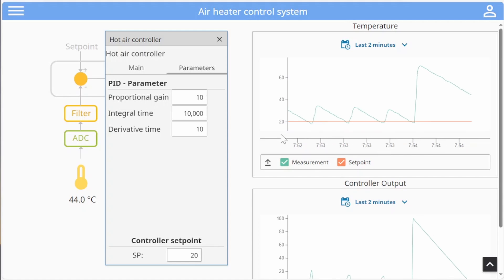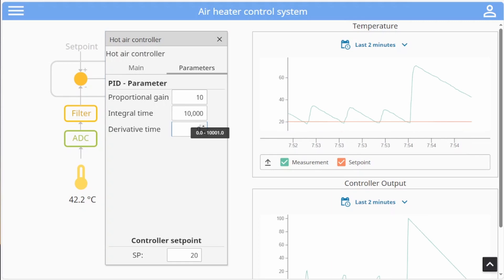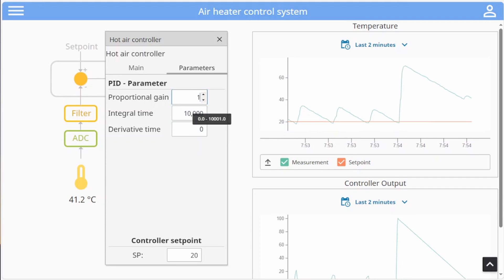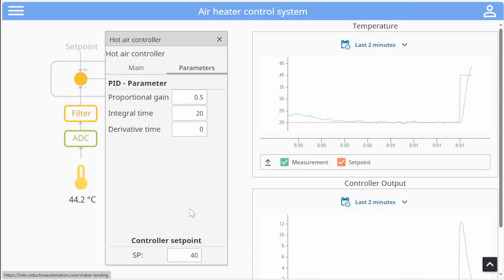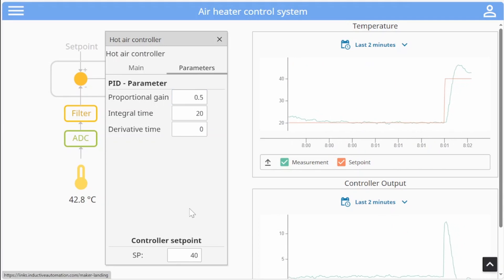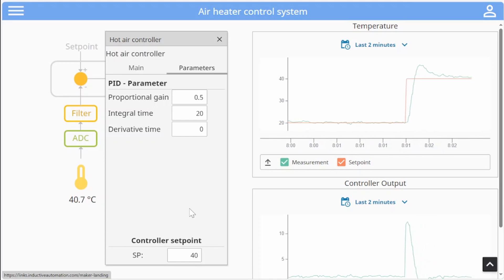To try to find better parameters we can start by setting the derivative time to zero and set the integral time to a very high value. We can then test different P gains and lower it enough to stop the oscillating behavior. I managed to find some good working controller gains and as you see the process responds good after a change in setpoint.